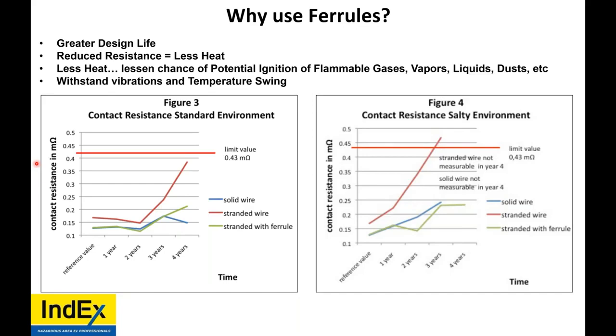So when you look at a salty environment, the one on the right, the one with stranded wire with a ferrule, lasts a long time. The one without a ferrule, a very short time. Now, the definition of ferrule has already been defined. It's not an insulated pin crimp that they used for this testing. By the way, after 5 years, the wires and everything moves every single day. Hot, cold, hot, cold. Metal expands and contracts. So your insulated pin crimps, you're still going to find more things coming up as to why they're not the greatest.